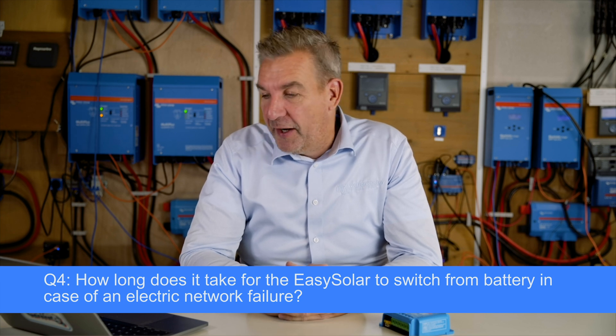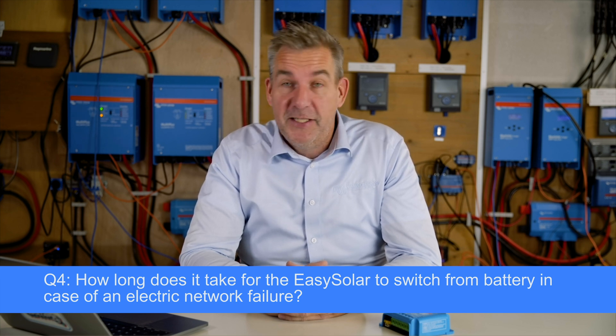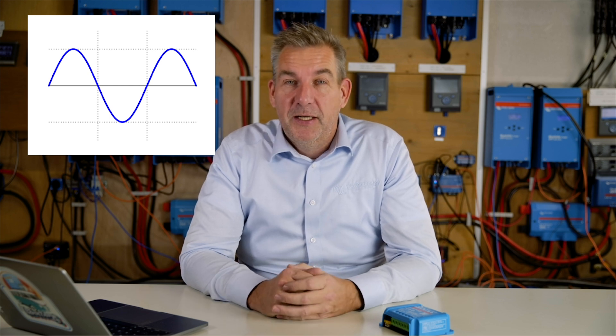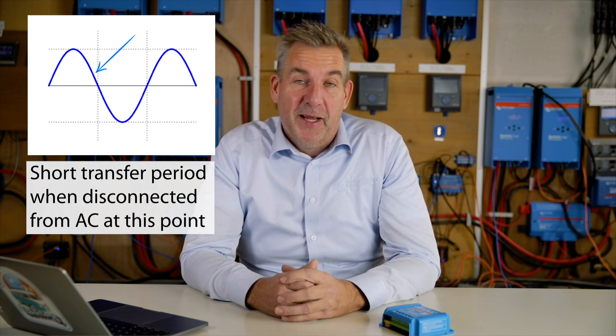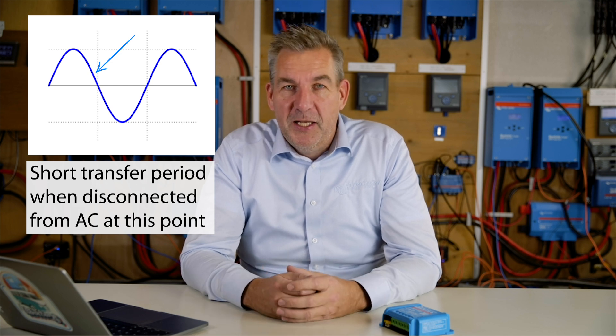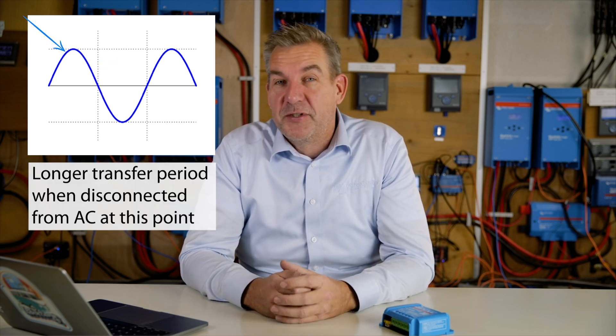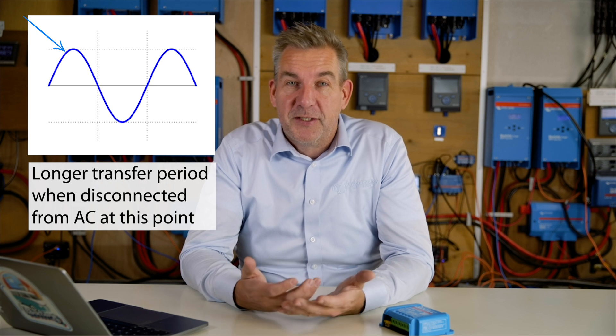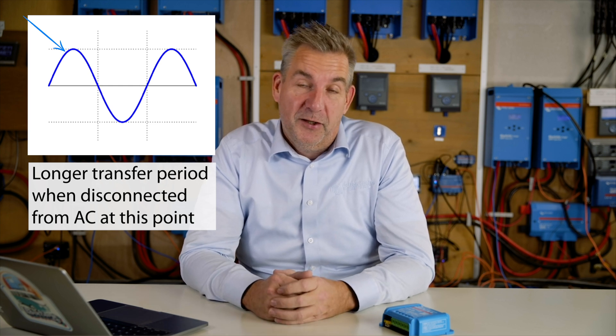The next question is from Marek, asking: how long does it take for the EasySolar to switch from battery in case of an electrical network failure? An EasySolar, just like a Multi and a Quattro, is constantly monitoring the input voltage. If the input voltage drops away, it switches over. Depending on which point of the sine wave the grid stops, if the sine wave is already going towards zero volts it's expected to be zero, so within 20 milliseconds the voltage would rise again and it would switch. If the voltage is at the top of the sine wave, the unit can react faster because a change is not expected — the switchover time is faster.